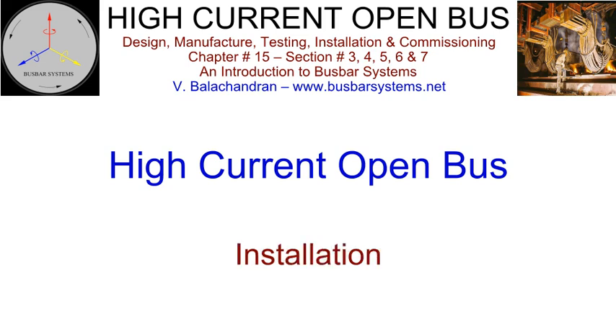Installation. Installation is a very important activity since most of the welding is carried out at the site. Prefabricated sections with flexible laminates, along with bought-out components such as insulators, structure, and fixings, are dispatched to the site and assembled. High-current open busbars are heavy and need mechanized contraptions for their installation. Aluminium welding forms the major portion of the installation of busbars in a metal extraction plant. Copper busbars with accessories are prefabricated at works and assembled at site with bolting or clamping.